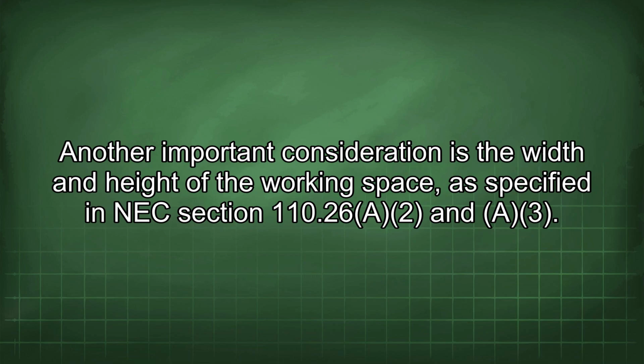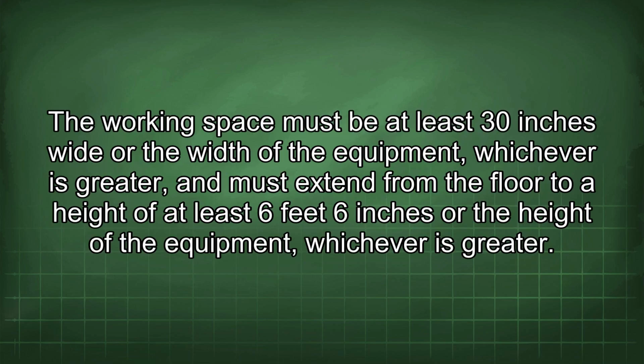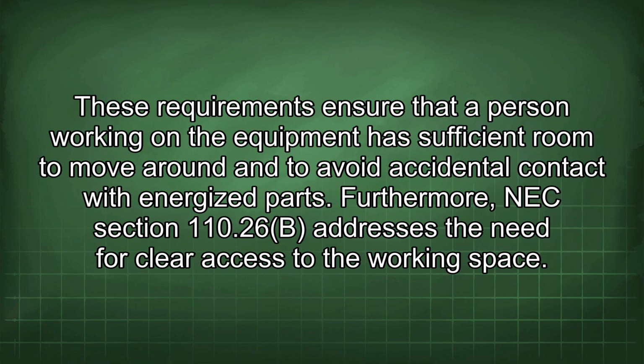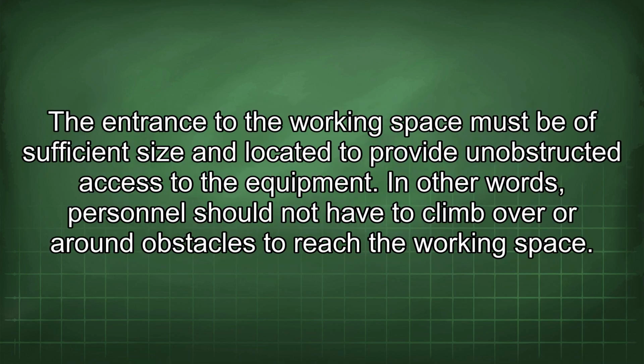Another important consideration is the width and height of the working space, as specified in NEC section 110.26(A)(2) and (A)(3). The working space must be at least 30 inches wide or the width of the equipment, whichever is greater, and must extend from the floor to a height of at least 6 feet 6 inches or the height of the equipment, whichever is greater. These requirements ensure that a person working on the equipment has sufficient room to move around and to avoid accidental contact with energized parts. Furthermore, NEC section 110.26(B) addresses the need for clear access to the working space. The entrance to the working space must be of sufficient size and located to provide unobstructed access to the equipment. In other words, personnel should not have to climb over or around obstacles to reach the working space.